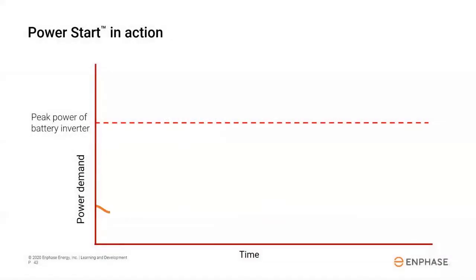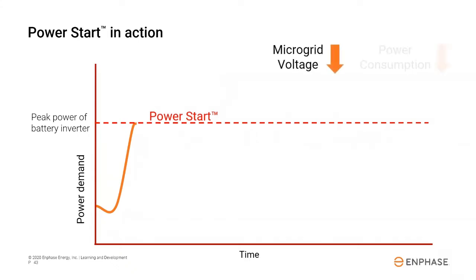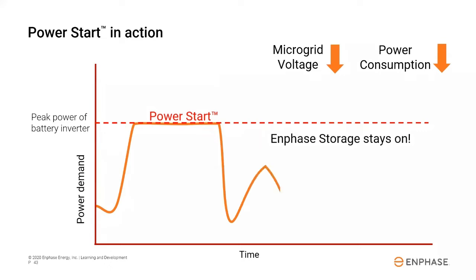The PowerStart algorithm detects demand spikes in a fraction of a second, and if the power demand approaches the peak power of the battery inverters, it reacts by instantly lowering the voltage, which in turn reduces power consumption. It's akin to a brownout, but on a very small scale and only for less than a second. And this really helps large appliances that have these large inrush currents start successfully with a smaller battery than you'd expect.